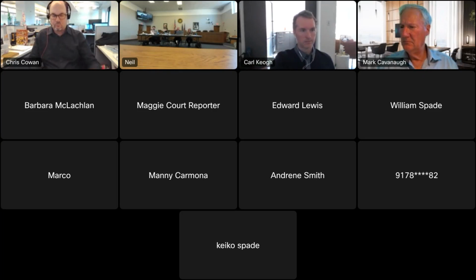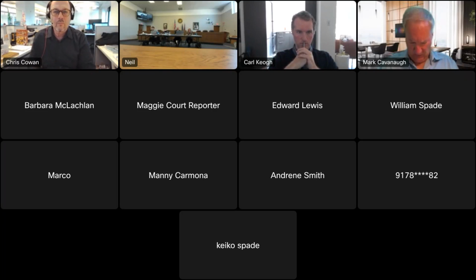I'll start by looking at the report and analysis provided. Could someone clarify, in the design of the sprinkler system, what the fire area of the design would be? Is it 1,500 square feet of the total space, per the light hazard occupancy, or is the entire space being designed to flow at once?